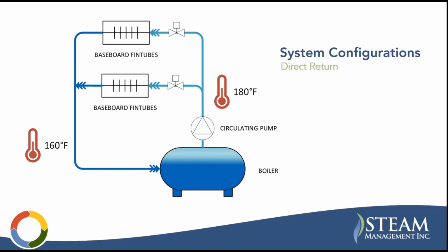This is called direct return. Now we're getting into some simple zones where you have balancing valves that promote the flow through each zone that you want. The disadvantage here is that you really rely on these balancing valves to force flow through to your more remote users. So that's the downside. This is for simple zoning applications, maybe medium-sized commercial buildings. This is also known as two-pipe direct return, so you'll hear that sometimes.